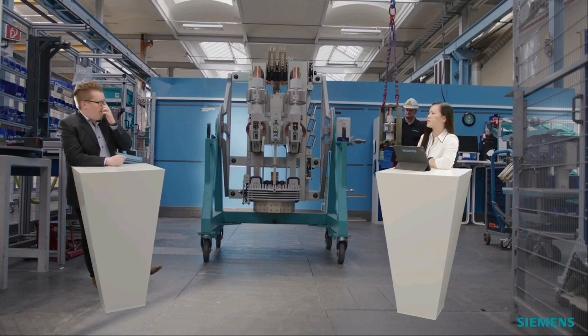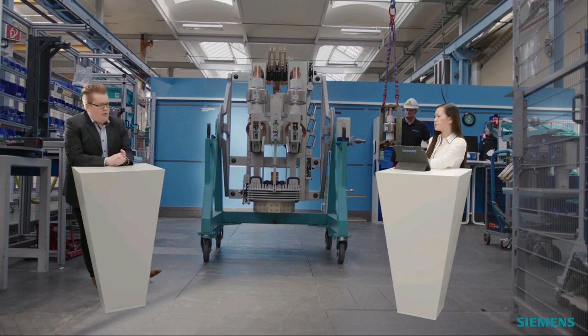Okay, so the 300 is given by the standard, or is this a Siemens specific value? The 300 volts is given by the standard. This is the minimum value. So when we are using the 300 volts as given by the standard, we are still calculating the absolutely worst case. Interesting. Can you give more insights on outer phase calculations?